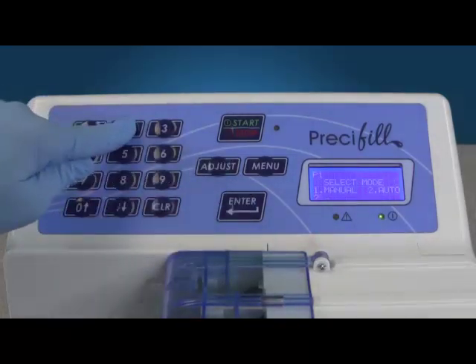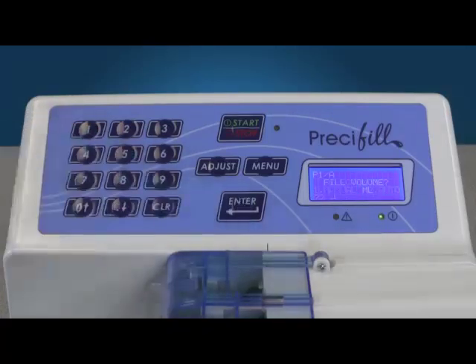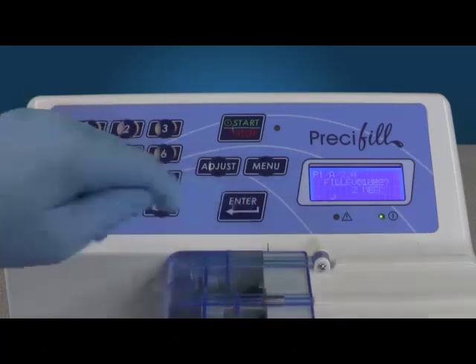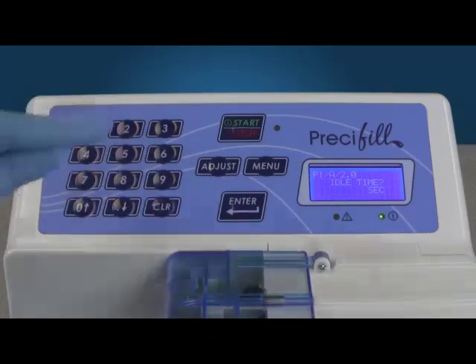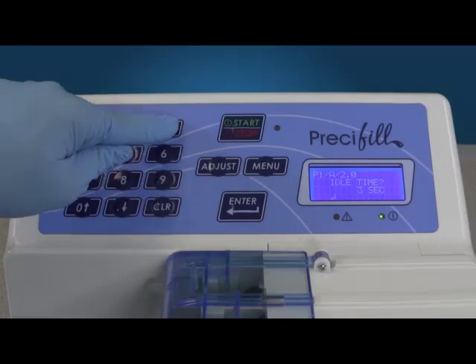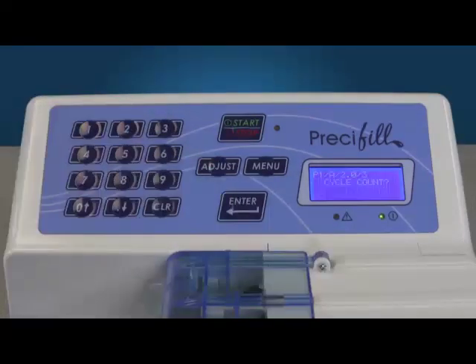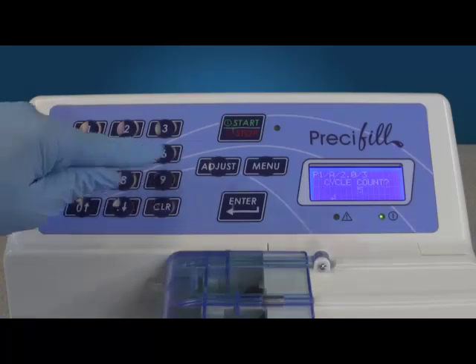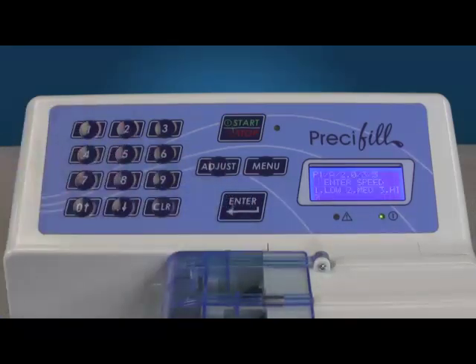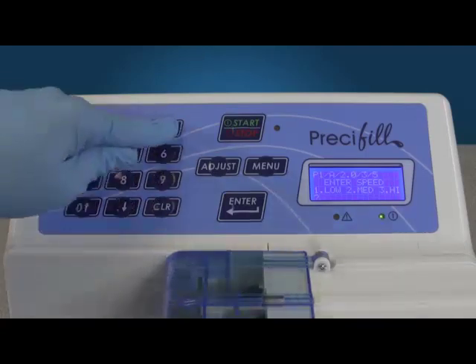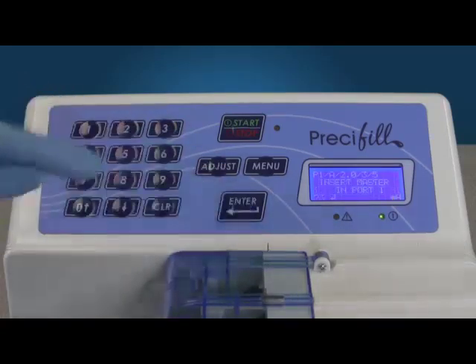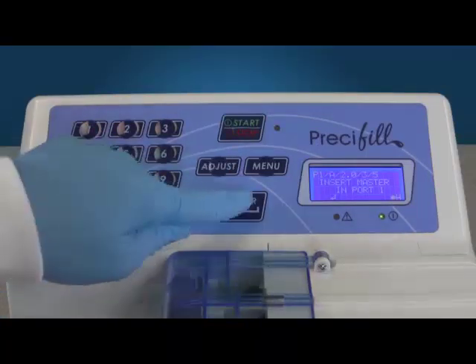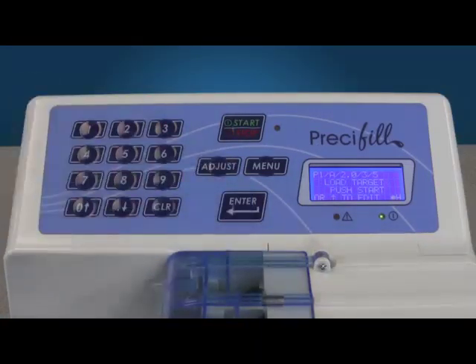Select the operating mode, in this case 2 for automatic, and press Enter. Enter the drug volume required in cc and enter. Enter the idle time, which is the number of seconds between fills, and enter. You have a choice between 1 to 99 seconds. Now enter the cycle count, which is the number of production fills to be completed, and press Enter. Select the speed, low, medium, or high, and enter. Confirm the master syringe is placed in the correct port, and press Enter.